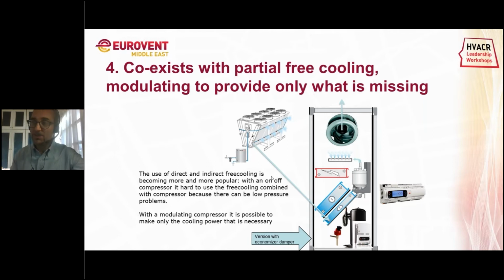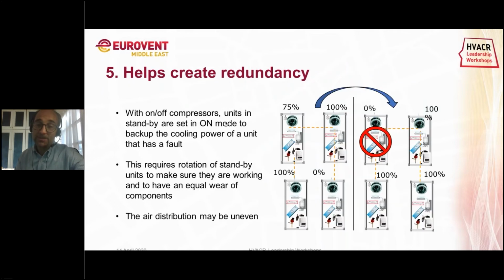Now, with the modulating compressor, it is possible to take advantage of partial free cooling, extending the running hours in free cooling mode, because the compressor, being capable of modulating, will give only the missing percentage. So it can be a version with a damper directly, or an additional coil, like the dual coil with an external heat exchanger with water, even using spray water. We know that water consumption combined with energy consumption is an issue too. Finally, another good reason why this technology is becoming very, very interesting is because it's changing the concept of redundancy.